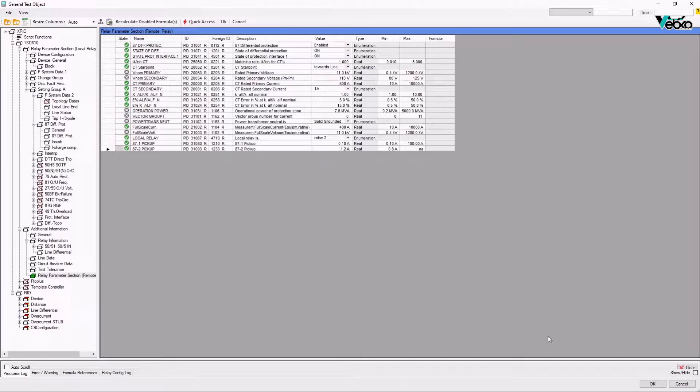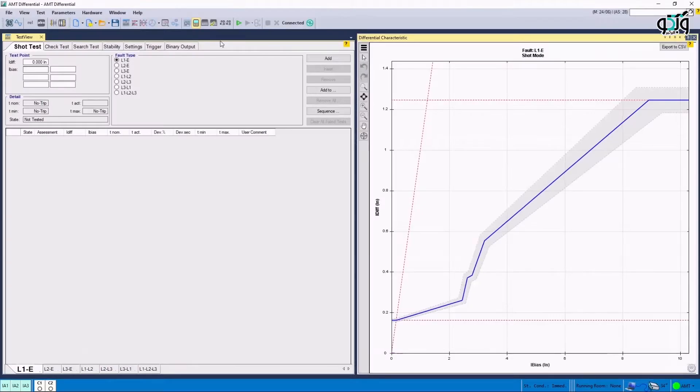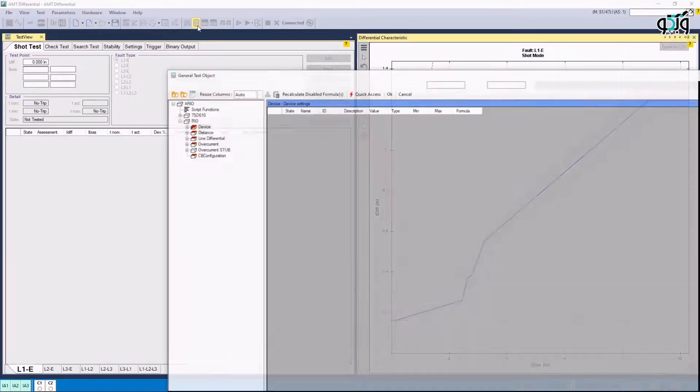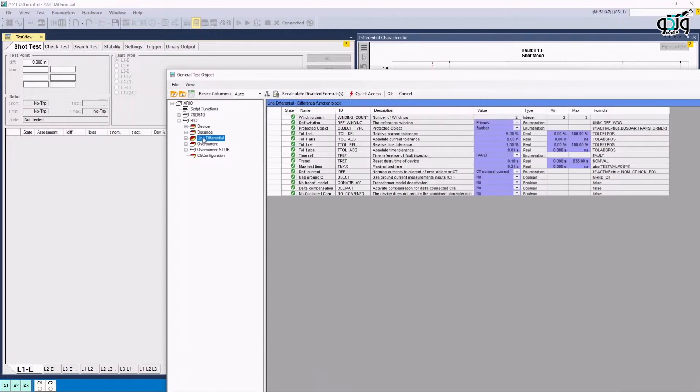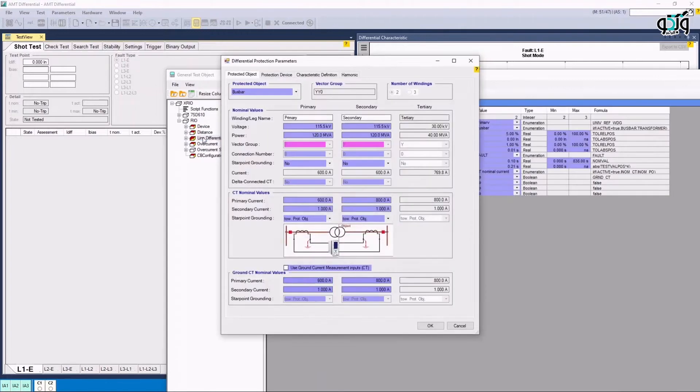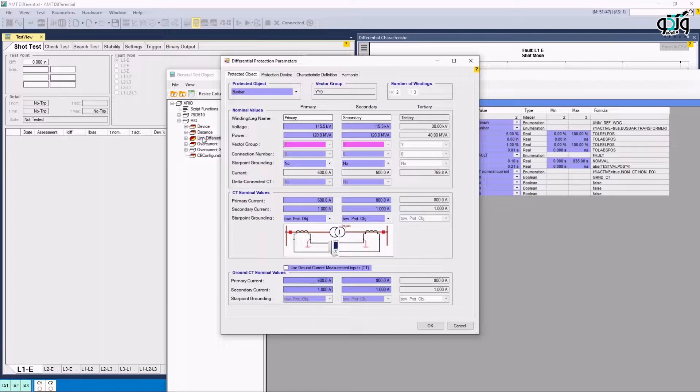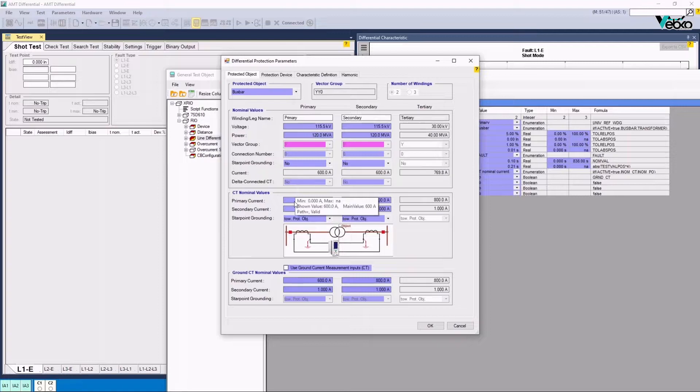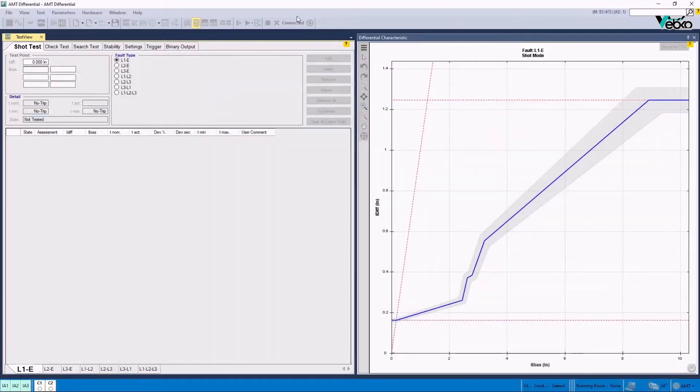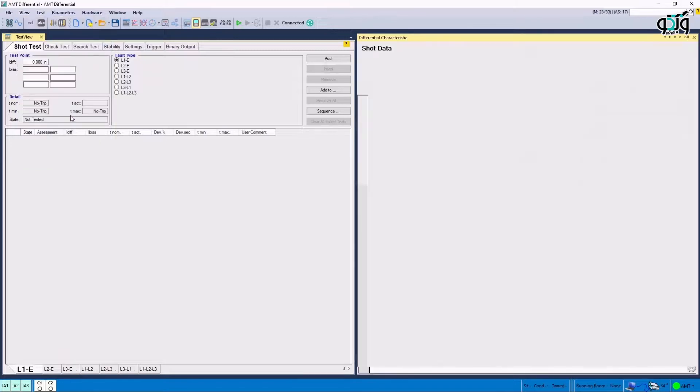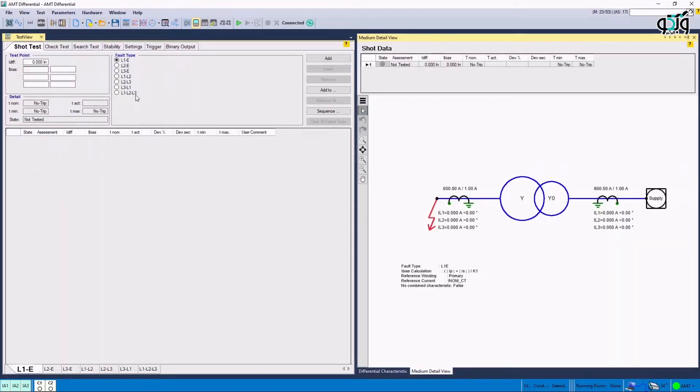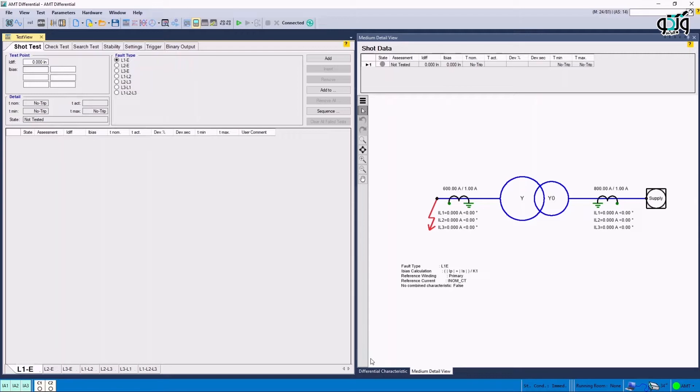Now, once more, Test Object Parameter is selected and Line Differential Block is opened by double-clicking on it. The important point here is that the value entered for primary and secondary in Protected Object section must be the same in both local and remote posts. Also, these values need to be reviewed especially in CT Nominal Values section to ensure that the turns ratio are correct. Also, it is possible to view the test status graphically along with the parameters on it by opening Medium Detail View window from the View menu. After finishing this stage, it is time to perform different tests.